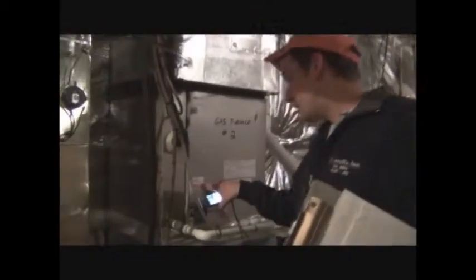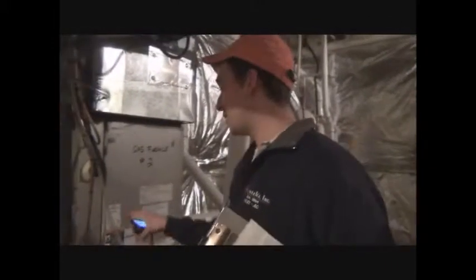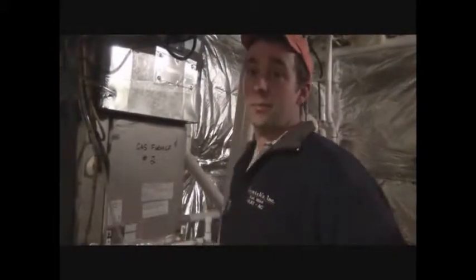Another thing we're doing is measuring the ductwork too, because you got to have a certain amount of square inches of ductwork to move the amount of air that you want. So we look here and we see CMPVP 4821. The 48 is our tonnage, so that's 48,000 BTUs, 12,000 BTUs per ton, making this a 4-ton system.